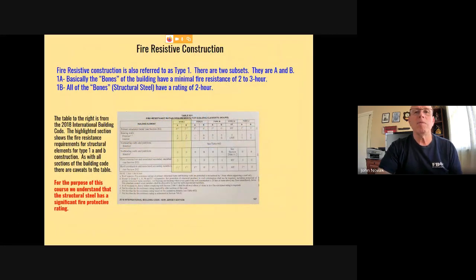So where is this coming from? Fire resistant construction is also known as type 1. With some of the other constructions, there were subsets, A's and B's. With fire resistant construction, we have type 1 construction. It could be type 1A, which means the bones of the building, the structural members, have a minimal fire resistance rating of anywhere from 2 to 3 hours. A 1B building, structural members have a rating of 2 hours. And this is right out of table 601 in the International Building Code.